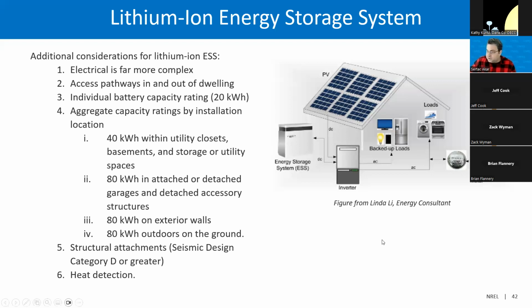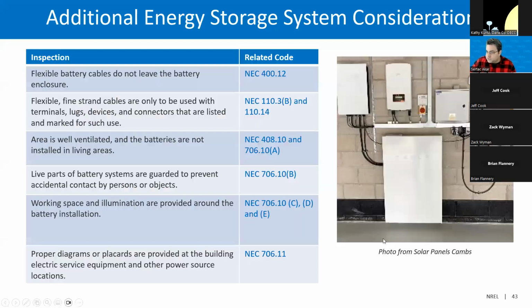So these are the main things to check in a lithium-ion energy storage system. Additionally, flexible battery cables must not leave the battery enclosure. Flexible fine strand cables must be used in terminals, lugs, devices, and connectors that are listed and marked for such use. Area must be well ventilated, and the batteries are not installed in living areas.